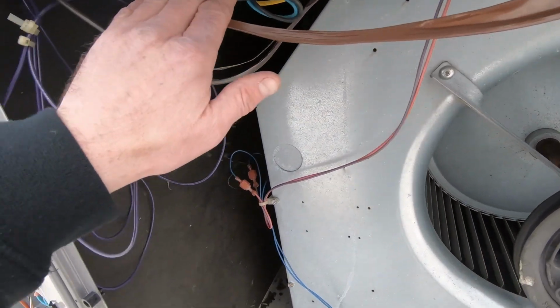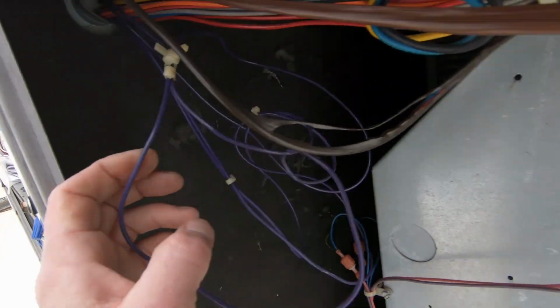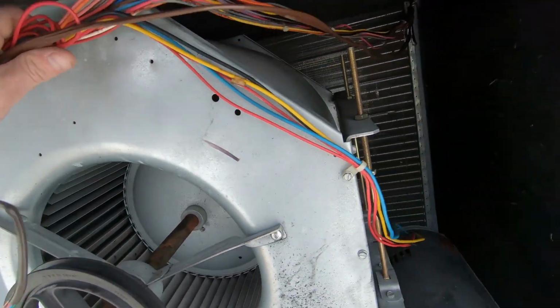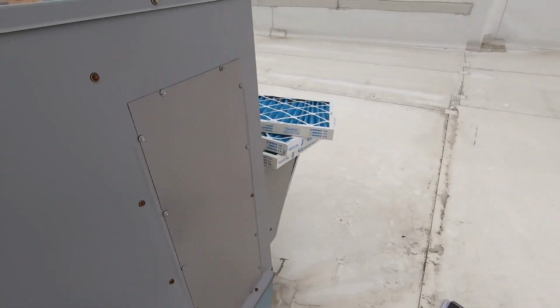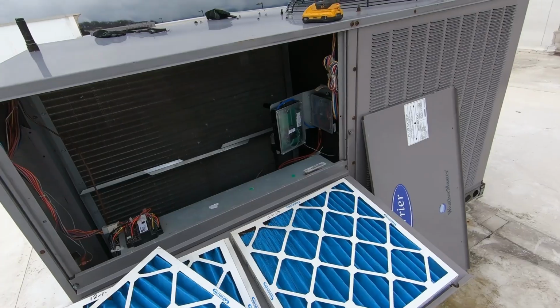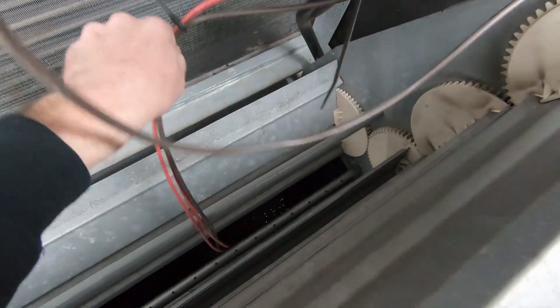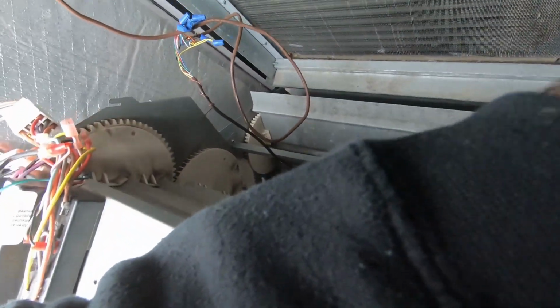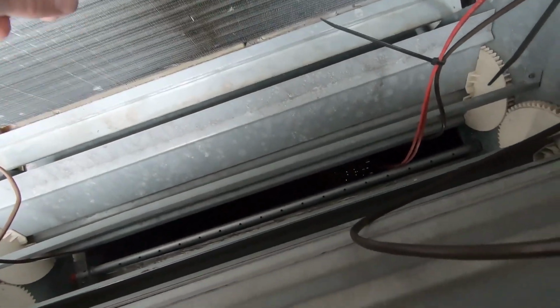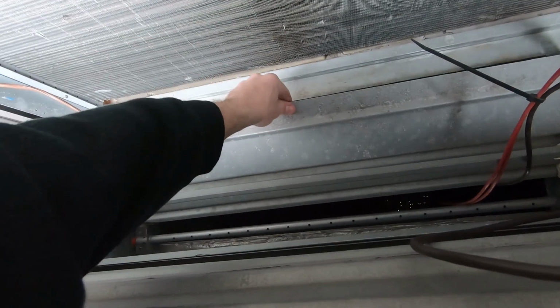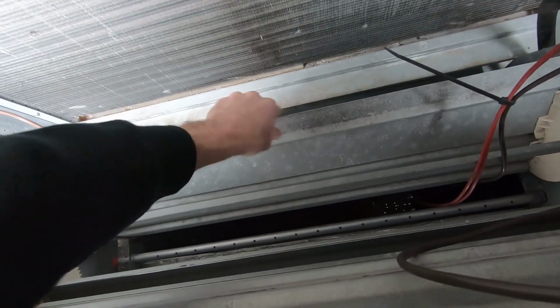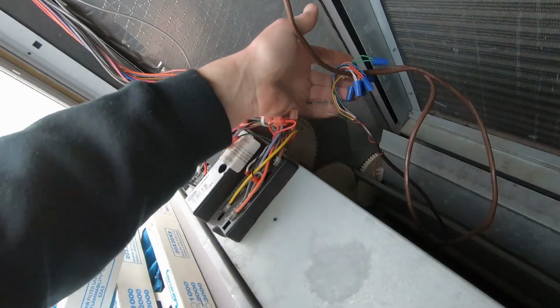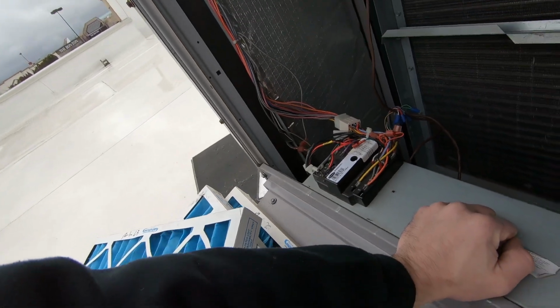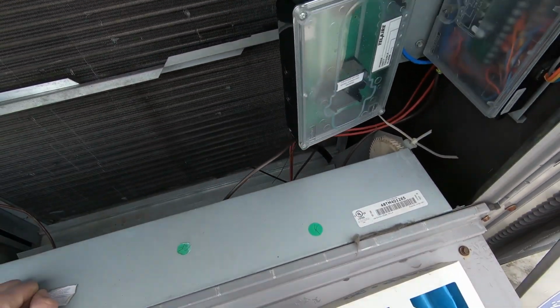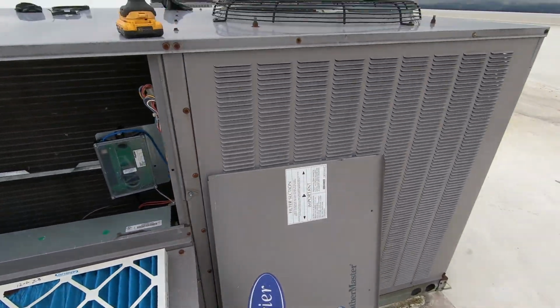We got to come back and thoroughly go through all the wiring and make sure we don't have any other issues. We need to reroute the wires so they're not running through the economizer. You have to find a different area to run the wires through. You can't just come up through the return. I mean, what happens when this economizer closes? It's just going to pinch the wires. Our DNE, or do not exceed, on this is very low, as it usually is, so I'm not making any repairs today. I'm going to document everything. I'm going to submit it, and we can come back.